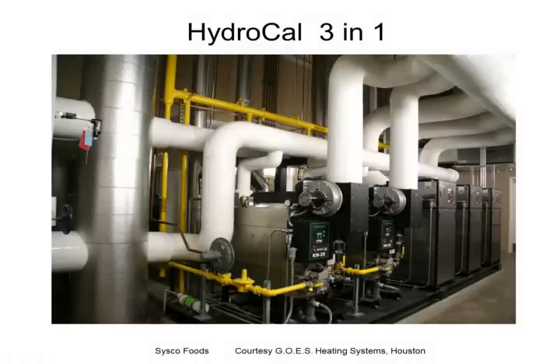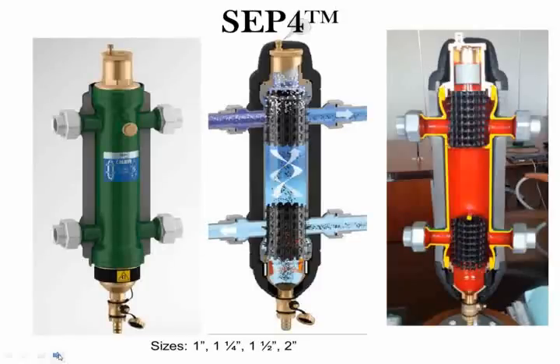Maybe it's vice versa. In the south of the United States, where you don't have high heat loads, perhaps a school in Houston, in the morning there might be a slight heat load, and it doesn't make sense to fire a high-mass, non-condensing boiler. You want to maximize your condensing boilers, so base load with your condensing boilers, and in those peak seasons where you have the most load, bring on your high-mass boilers. So it's a great opportunity with the HydroCal to combine mixed boilers.